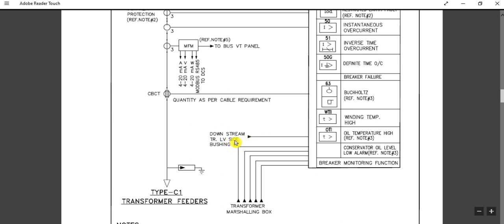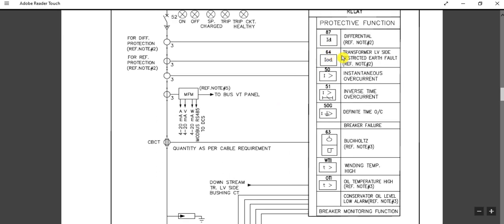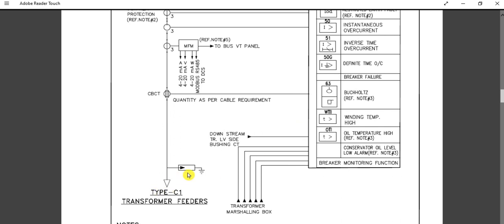The downstream transformer low voltage side bushing CT is also shown here. This is for the 64 relay — the transformer restricted earth fault protection. For this purpose, we need the phase-side CT connection on the high voltage side, and one CT connection from the downstream transformer low voltage side bushing CT. That bushing CT signal is also required for the operation of the 64 relay.